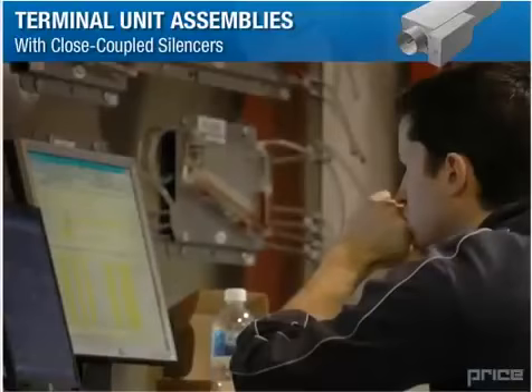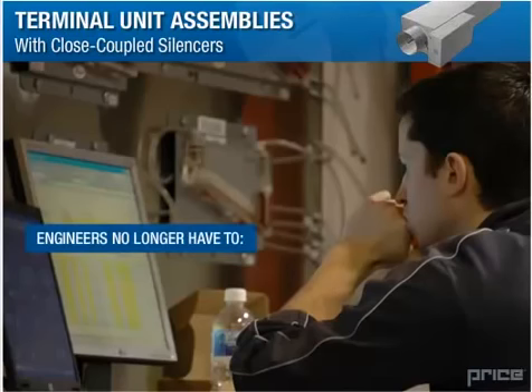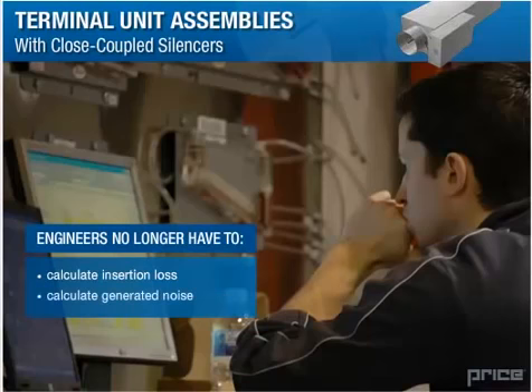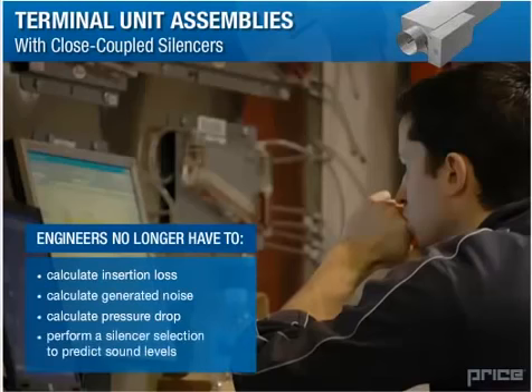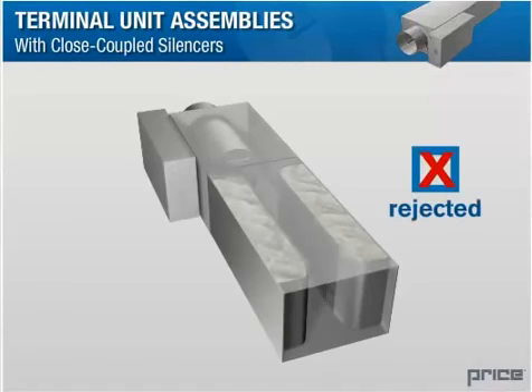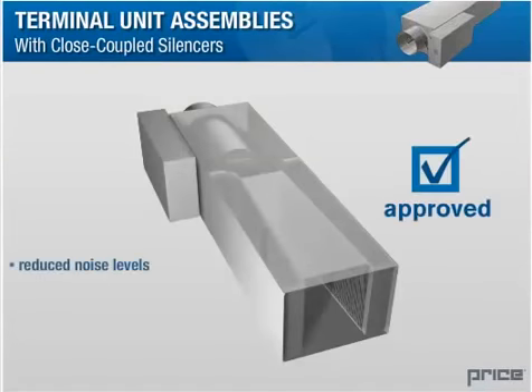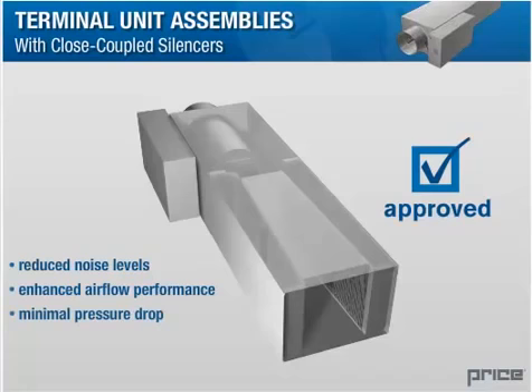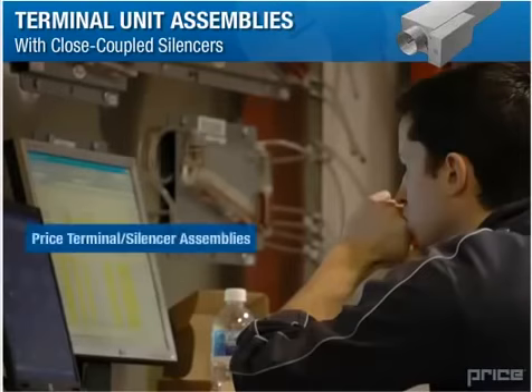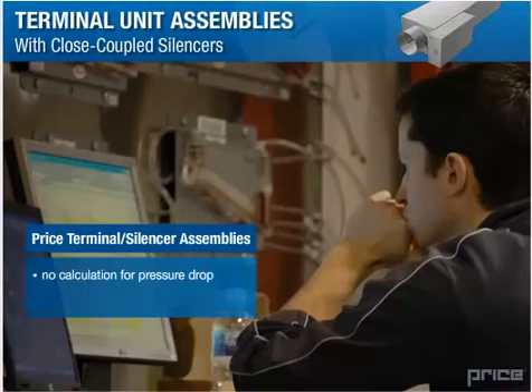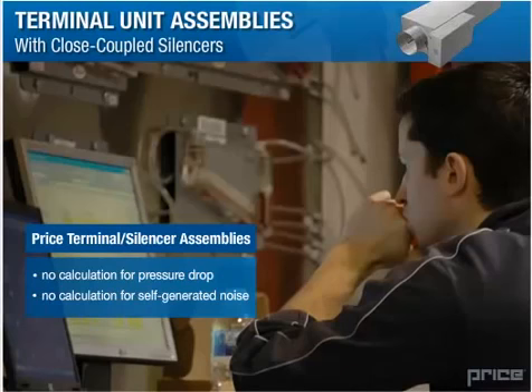The importance of having a fully certified and tested terminal unit silencer assembly for noise-sensitive applications is that design engineers no longer have to calculate insertion loss, generated noise, pressure drop, or even perform a silencer selection to predict sound levels, which in reality may be inaccurate. Furthermore, Price has done extensive testing to develop internal silencer geometries that greatly reduce the noise levels of the terminal units without sacrificing airflow performance or creating more pressure drop within the HVAC system. In other words, engineers will no longer have to allow for silencer pressure drop or self-generated noise within their systems when they want to specify a Price terminal silencer assembly.